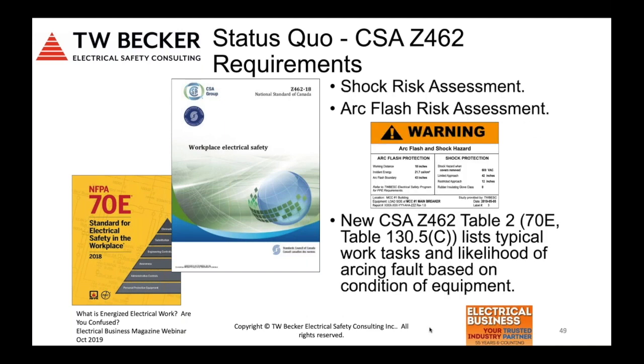So again, the shock risk and arc flash risk assessments, that's an example of a detailed arc flash and shock warning equipment label. I have a lot of concerns too that unfortunately over the last 10 years with the incident energy analysis studies completed, there's a lot of non-compliant labels out there, but if the qualified electrical workers are trained properly, they would identify these labels, bring them to the attention of their supervisor, and we can get that information sorted out too. Again, the new Table 2 that I indicated for the arc flash risk assessment specifically with the work task list, condition of maintenance, likelihood of occurrence of an arcing fault and arc flash, yes or no, but it is a subjective based table. And I'm really encouraging industry to not be conservative when you're determining condition of maintenance. You have to be realistic and reasonable in your determination.